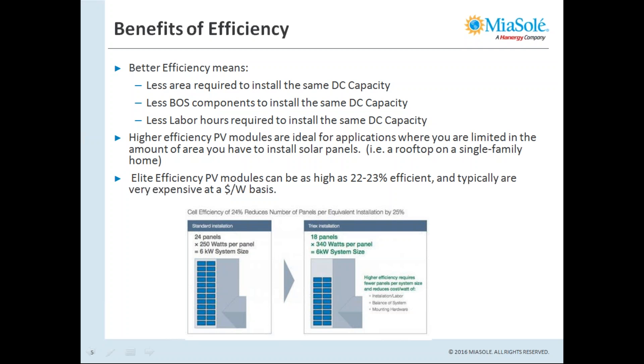Looking at the diagram at the bottom of the presentation, you can see a 24-panel system made up of 250-watt panels equating to a 6-kilowatt system. The home on the right that uses 340-watt modules needs 25% less space to equal the same 6-kilowatt system. That's a clear example of how efficiency can be a benefit. High-efficiency PV modules are usually more expensive at a dollar-per-watt scale, so you have to calculate the trade-off between paying more for the panels versus the balance-of-system and labor savings.